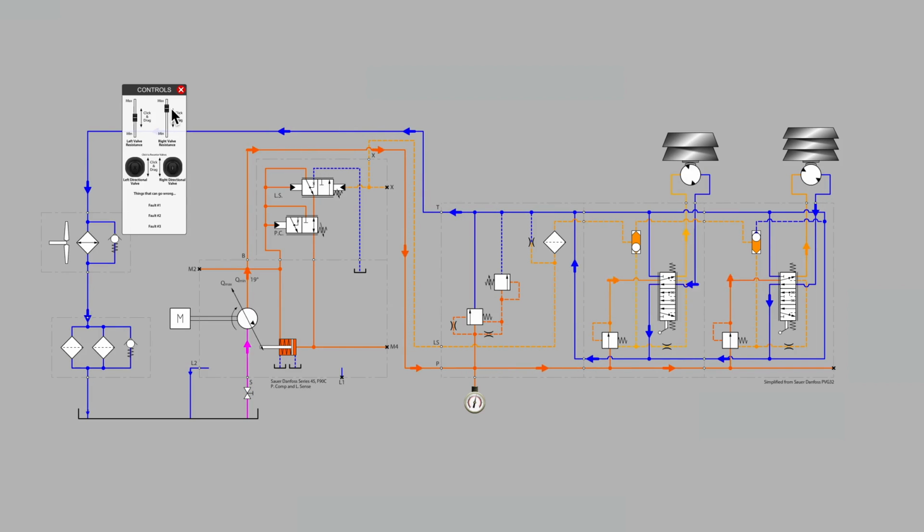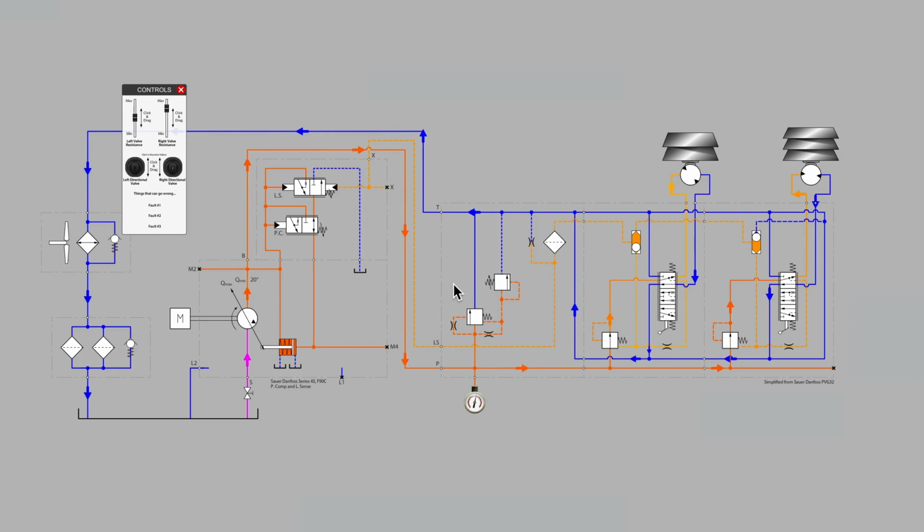The only other major feature that we didn't speak of is the relief valve that is present at the pump inlet section of our valve bank. But since we're using a pressure compensated and load sense capable pump, this relief valve section should see very occasional, if any, use at all. Our pressure controls are handled at the pump.